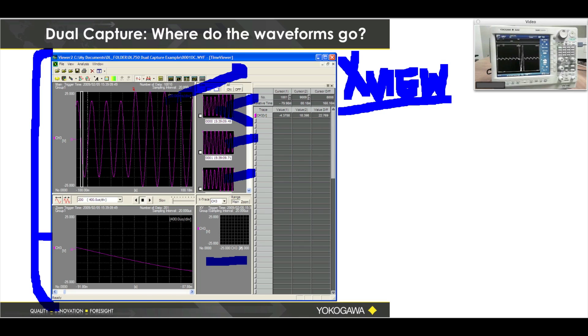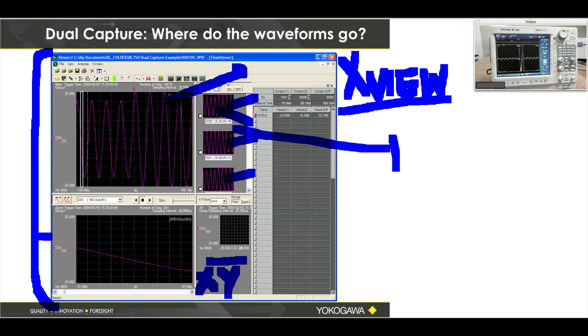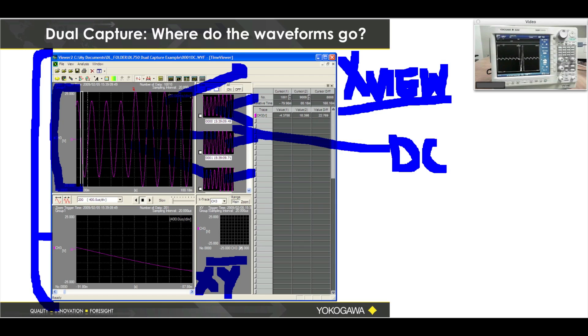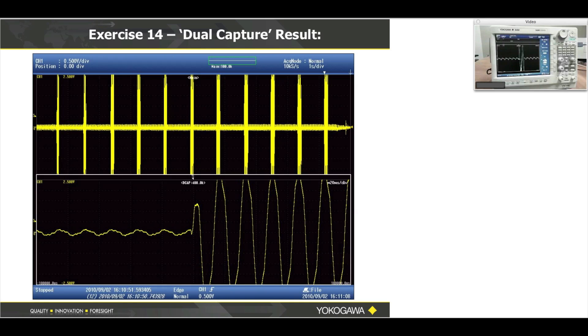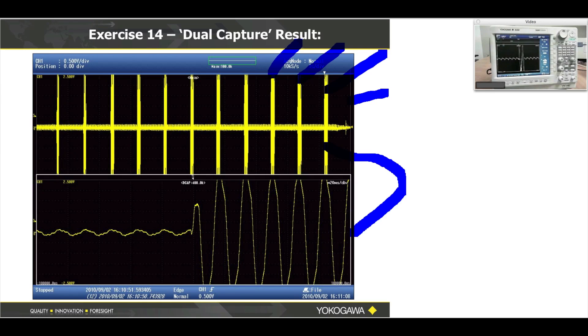There's also an XY window, though not many customers use that. Here's the dual capture window — those are your dual capture events. And this main window is where you can put each of those events and look at them separately, enable them simultaneously, and look at them overlaid with one another. This is a successful dual capture test — the top window is the main window, and each event is displayed at a shorter time base at the bottom.